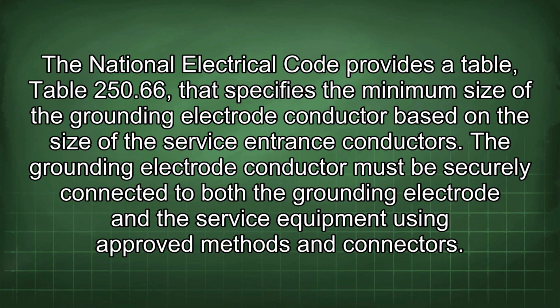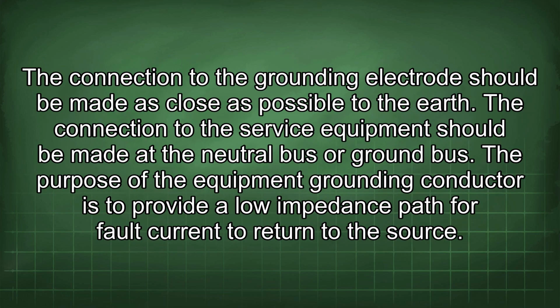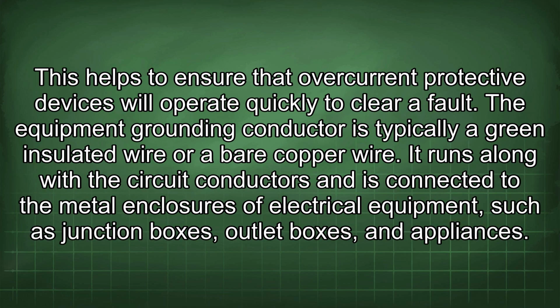The grounding electrode conductor must be securely connected to both the grounding electrode and the service equipment using approved methods and connectors. The connection to the grounding electrode should be made as close as possible to the earth. The connection to the service equipment should be made at the neutral bus or ground bus. The purpose of the equipment grounding conductor is to provide a low impedance path for fault current to return to the source. This helps to ensure that overcurrent protective devices will operate quickly to clear the fault.